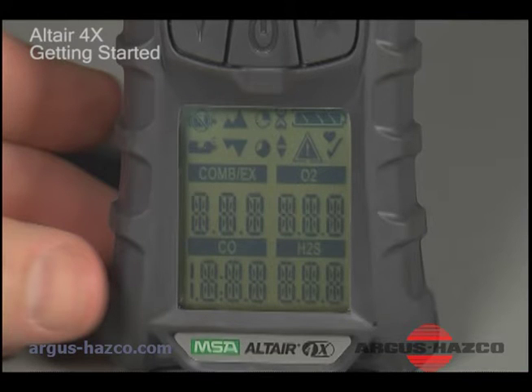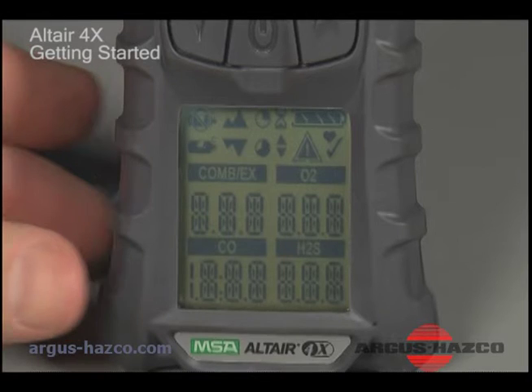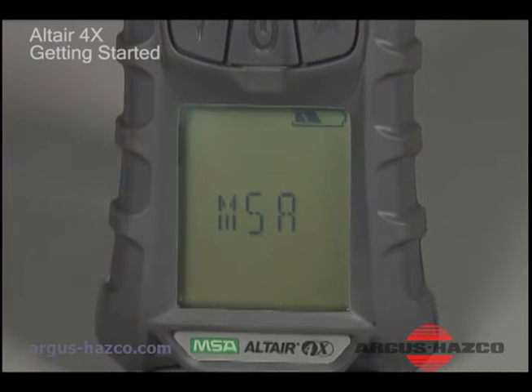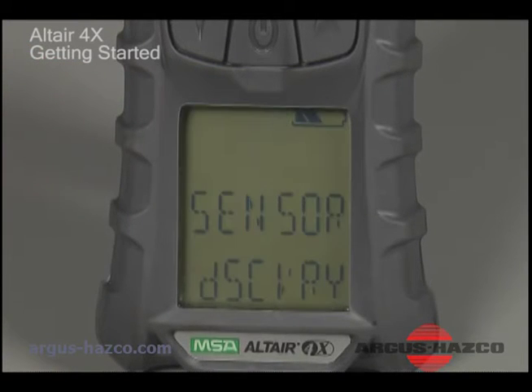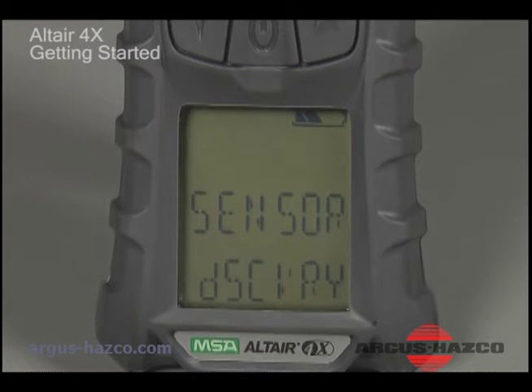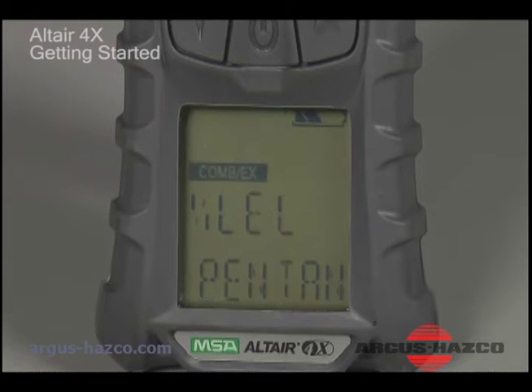During the startup sequence, the unit will perform an alarm and display self-test, display various information including software version, perform sensor discovery to verify sensor configuration and communication, and display alarm set points.